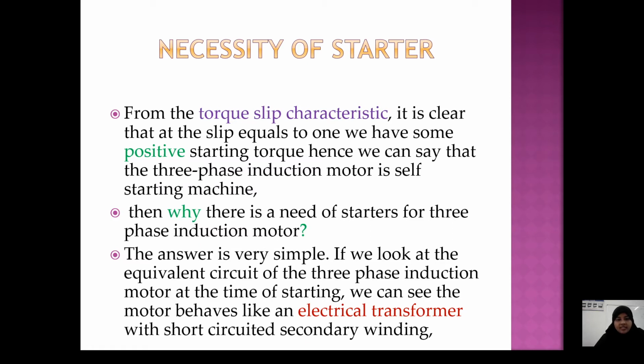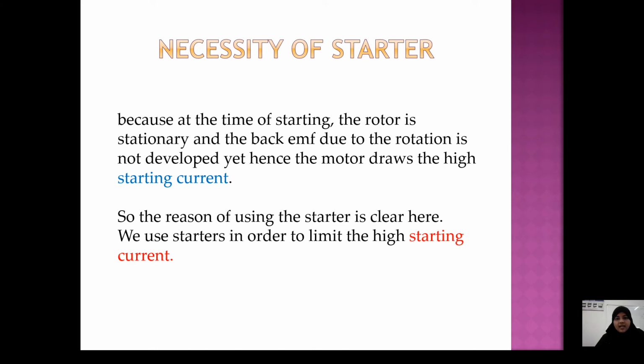So when we see the equivalent circuit of a three-phase induction motor at the time of starting, the motor will behave like a transformer with short-circuited secondary winding. Because at the time of starting, the rotor is stationary and back EMF due to rotation is not developed. The motor will draw high current from the supply, so we require a starter to limit this high starting current.